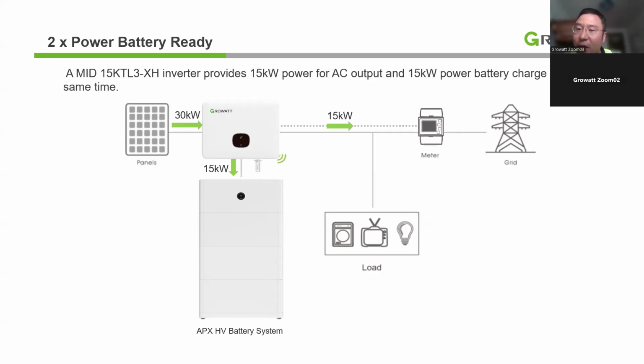If there's no battery on site, it's only a solar system, and the CER only allows 133% DC oversizing for a solar system. But as long as there's a battery on site, it's no longer a solar system, it becomes an energy storage system, and for an energy storage system the CER does not have that limitation. It's all based on the statement of the manufacturer.